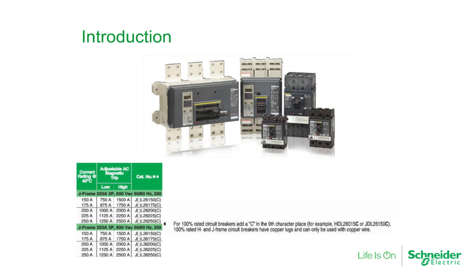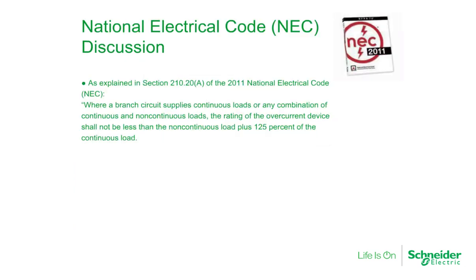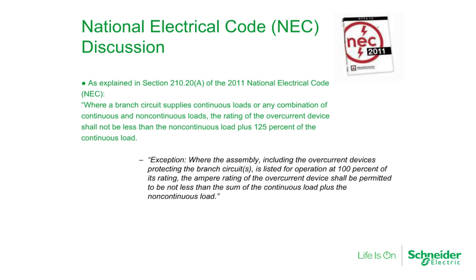Let's discuss how the NEC and UL set the rules about 100% and 80% ratings. According to the 2011 National Electrical Code, the rating of the overcurrent device shall not be less than the non-continuous load plus 125% of the continuous load. There is an exception that allows for 100% rated breakers to be used in equipment tested and listed for 100% rating, which has led to the phrases 100% rated breakers and 80% rated breakers.